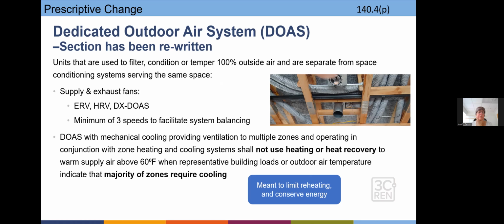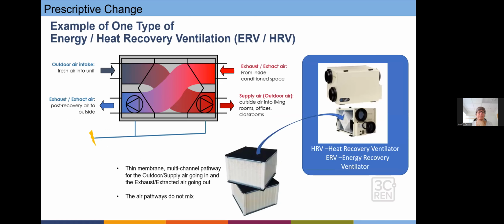ERV and HRV might be new terms to folks. Here's an example of a small scale ERV, energy recovery ventilation, or HRV, heat recovery ventilation. Through these special membranes, the air going out of the building and the air coming in for fresh outside air don't literally mix, but they pass through the membrane so those thin surfaces can transfer heat to one another very easily, recapturing some of that heat from the exhaust air. It also works the same way for air conditioning mode, but most of the time these are used to capitalize on conserving heat going out of the building.